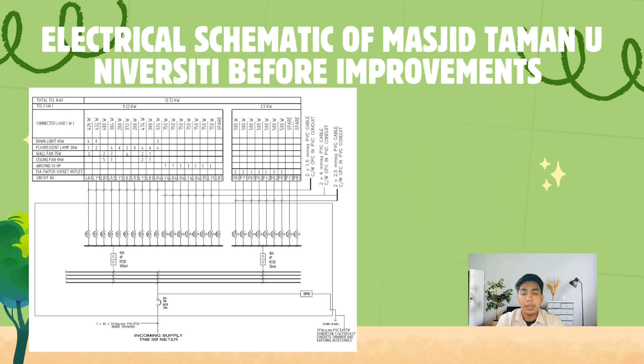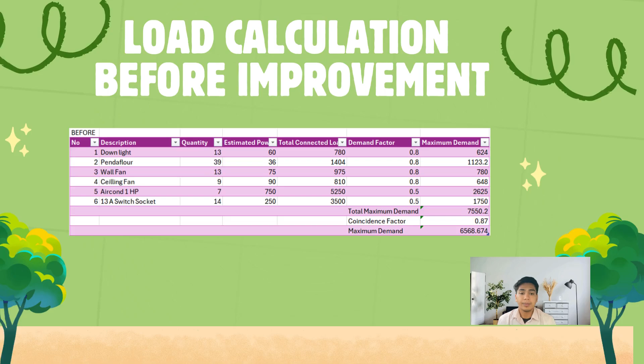Next, the load calculation before improvement. We calculate the total power load based on existing equipment: 13 units of 60-watt downlight, 39 units of 36-watt fluorescent Pendaflour light, 9 units of 90-watt ceiling fan, 13 units of 75-watt wall fan, 7 air conditioners of 1 horsepower, and 14 sockets of 13 ampere. The maximum demand was around 6,568.67, which was very high considering the lighting quality and cooling effect.